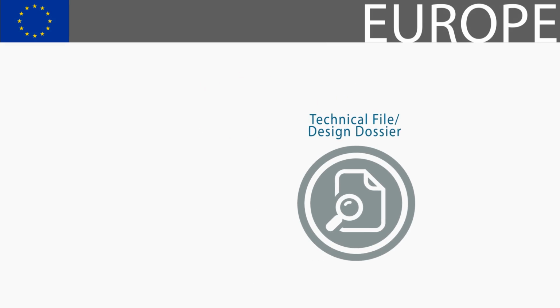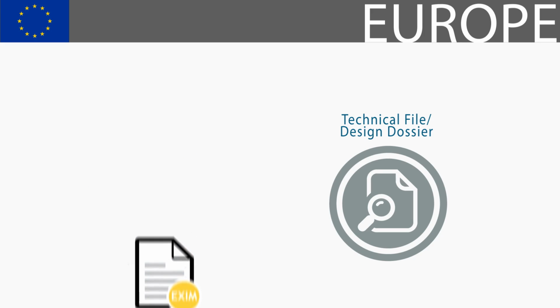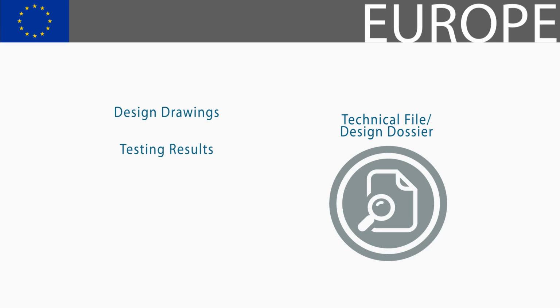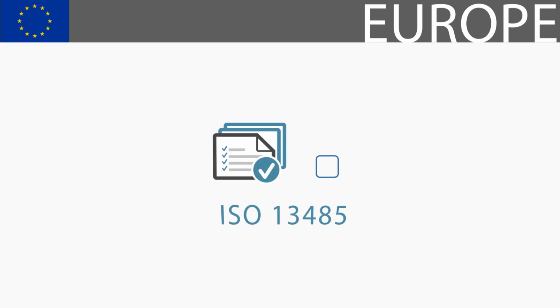A key part of the certification process involves the compilation of a technical file or design dossier. This collection of documentation contains extensive details about your device, including design drawings, testing results, clinical evaluation reports, instructions for use, and a risk analysis. You'll also include a copy of your ISO 13485 certificate.